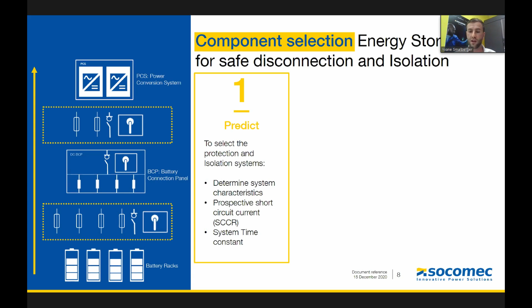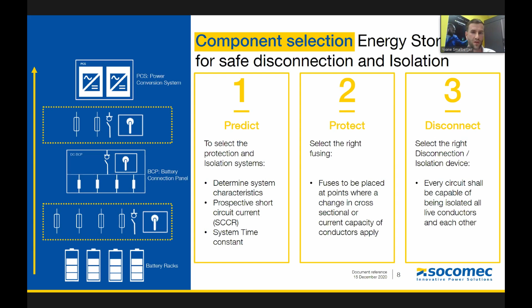After predict, we have protect. Protect means we select the right fusing or protection systems, following the standards where it says fuses need to be placed at points where there is a change in cross-section of the conductor or current carrying capacity of the conductor. And finally, disconnect. So choosing the right disconnection device or isolation device, every circuit shall be capable of being isolated from live conductors and from each other.